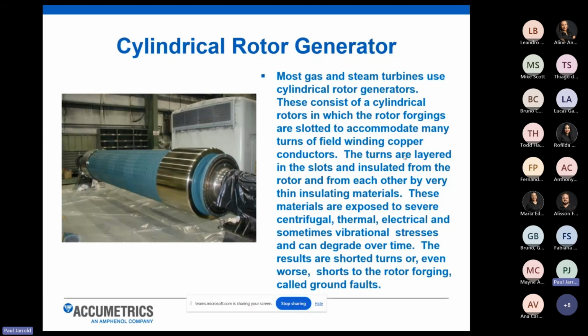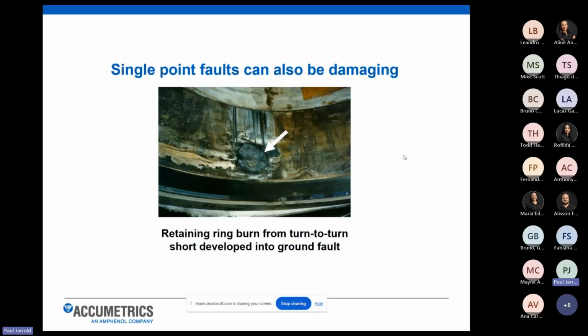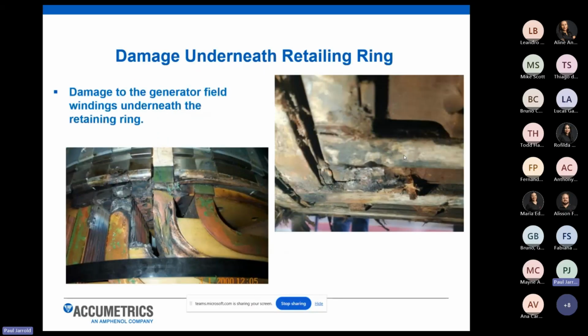forging. So this is a case where a customer had a single point fault. A double ground fault is the worst case scenario. However, a single point fault can also cause damage to the retaining rings. In this case, on each end of the cylindrical rotor, the fault happened and burned into the retaining ring, causing the unit to have to be shut down. And here are some more images of what that damage looks like underneath that retaining ring.